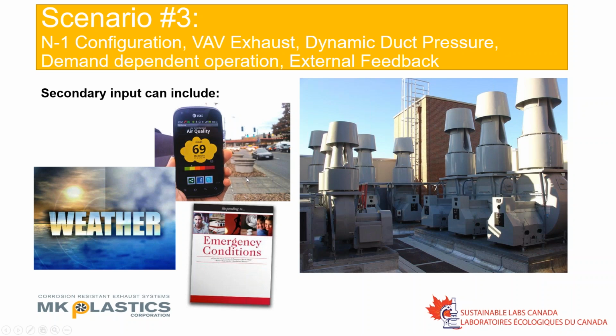The same thing will be with the monitor for the air quality of the lab, in other words, the contaminants that are in the exhaust duct. If the contaminants are noted to be high, then we will turn on maybe more fans or increase the volume of the fans to remove it. And if the contaminants in the duct are less, then I will turn the unit down accordingly. Obviously, at some point, we can only turn it down so far. So if the number of air changes goes down to a number where the exhaust fans are not meeting the 100 feet per minute face velocity, then we need to increase the static pressure or change the air accordingly going through the fans. Therefore, the brake horsepower will change.